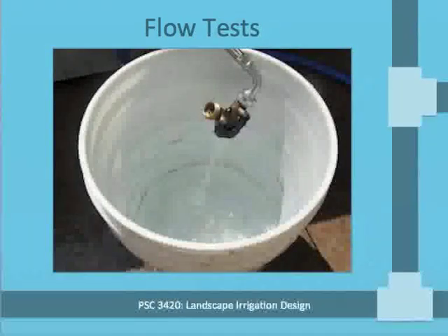On some projects, the flow of water from the source to the point of connection passes through pipe or valves, or sometimes other system components that you can't identify. And when that's the case, you can use a flow test to determine the design capacity and the pressure available for sprinkler operation. That provides you with an approximation of the flow available at varying pressures, or it can also be used to provide the pressure available at varying flow rates.